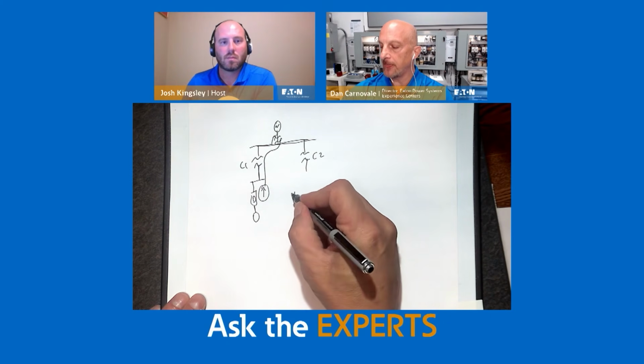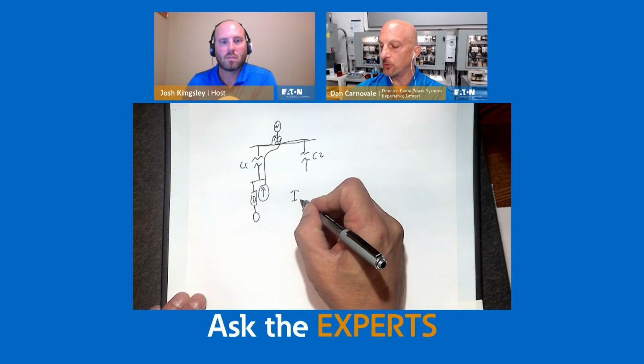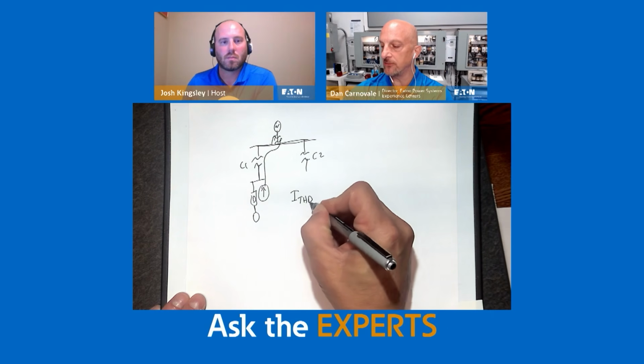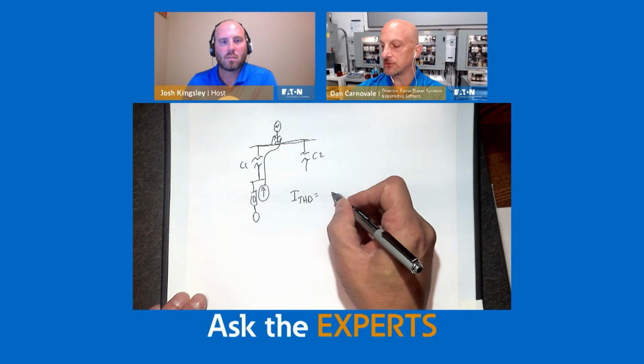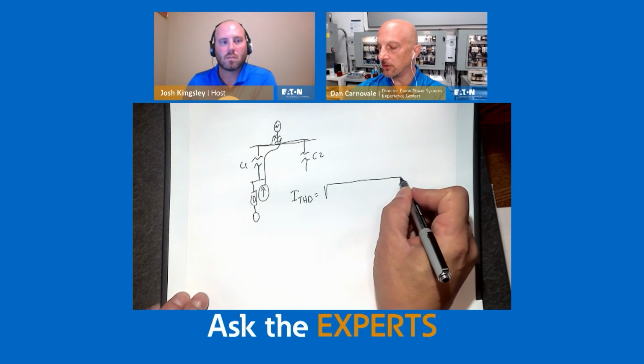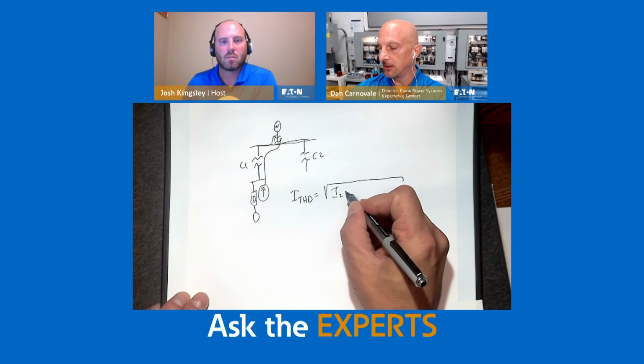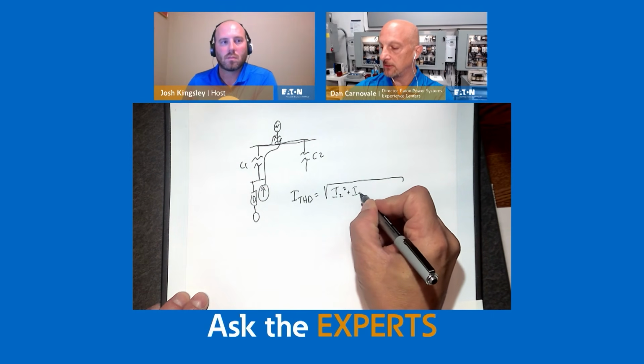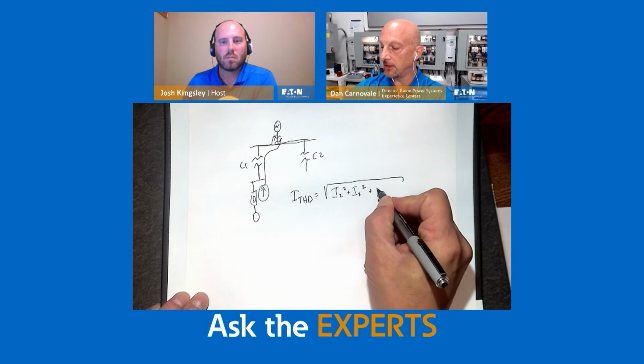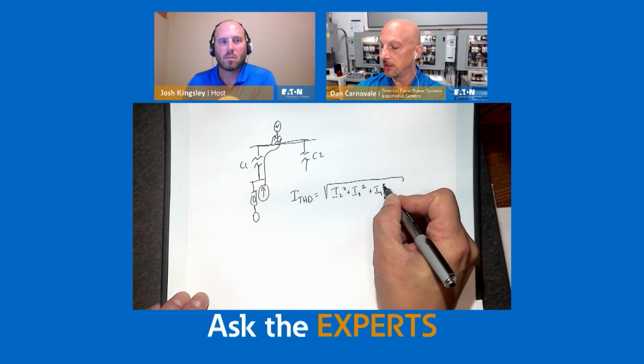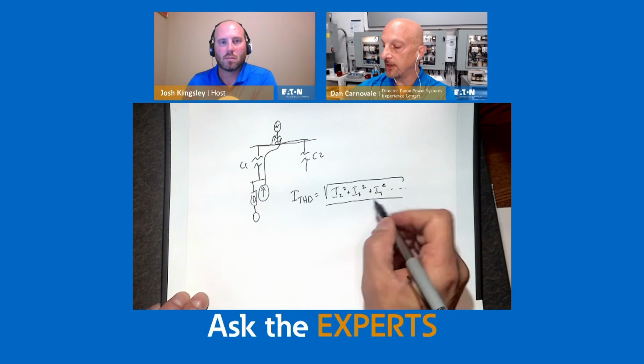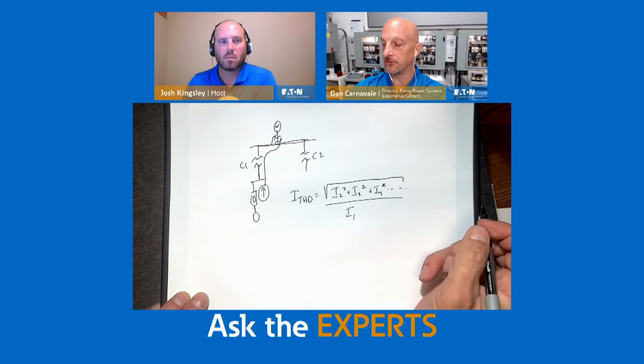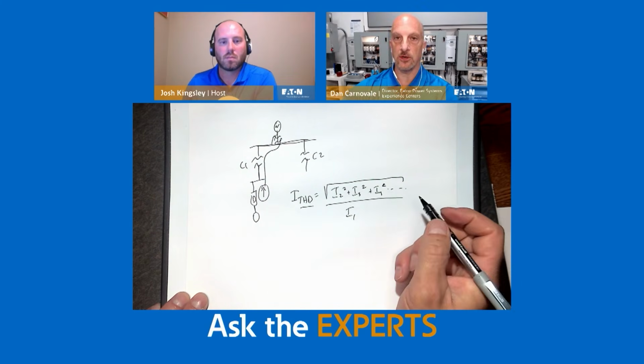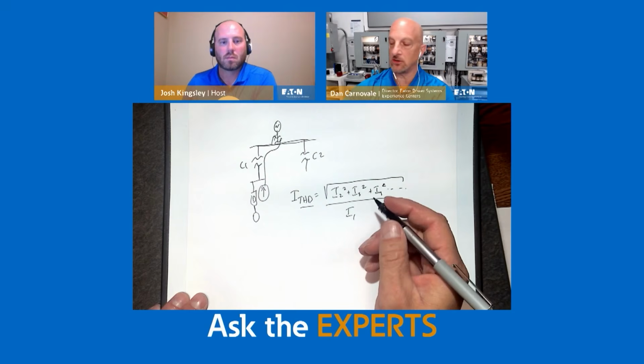We use a term called ITHD. What's ITHD? It's total harmonic distortion. That's the sum of all the harmonics, I2 squared plus I3 squared plus I4 squared, dot, dot, dot, whatever, divided by the fundamental, the 60 hertz. That's THD, total harmonic distortion. And at any given time, you can calculate that.